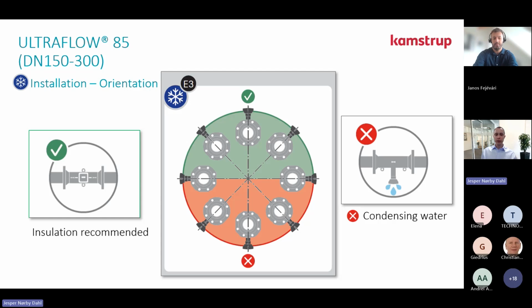When talking about cooling, again, we recommend insulating the flow sensor. Here, we recommend that you only install the flow sensor in the upper half circle. And this is, of course, to avoid condensation dripping down all the time into the display. Of course, the display and the whole flow sensor set is IP68, but still we do not recommend installing it in the lower half circle, and this is just to avoid the cavitation, the condensation.